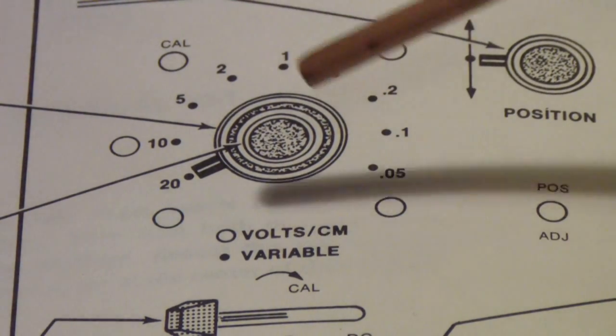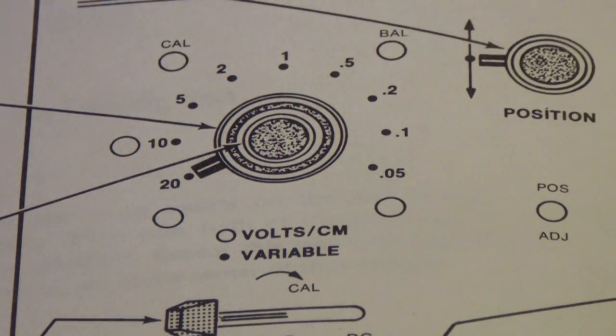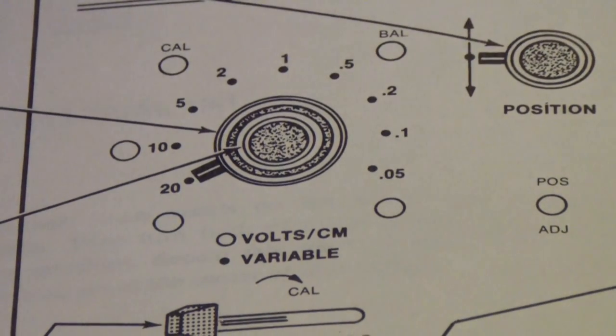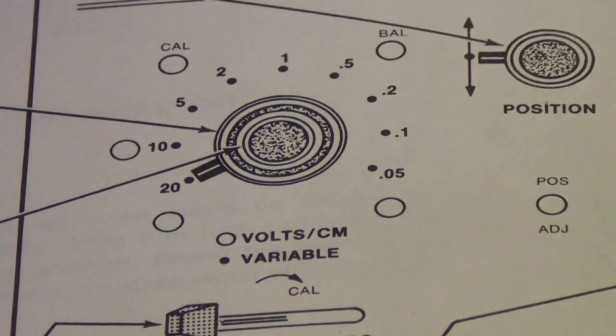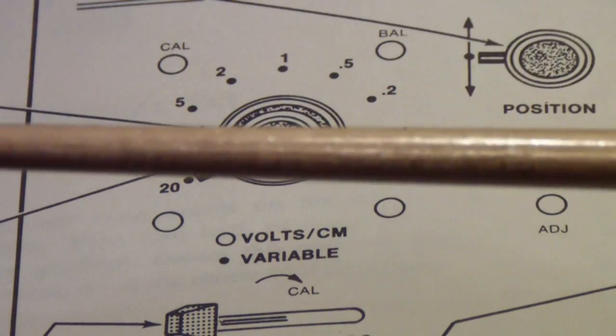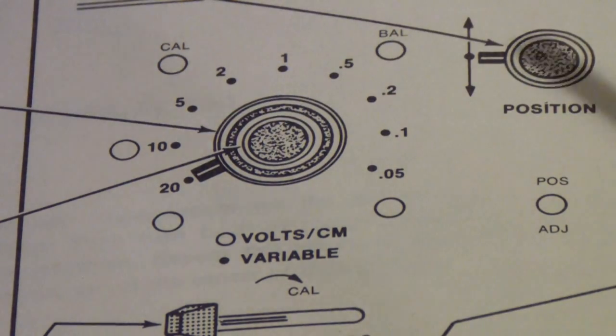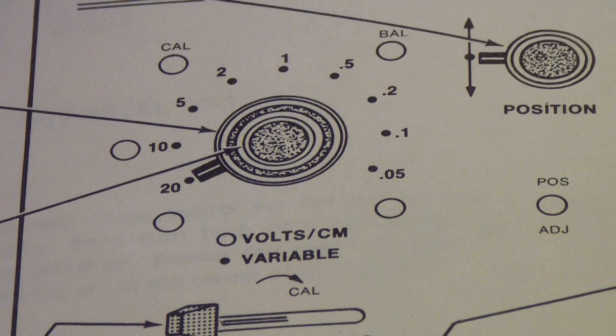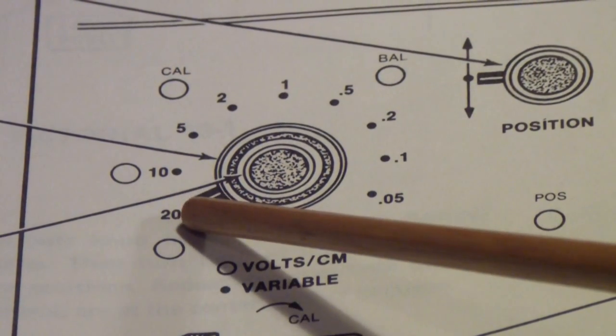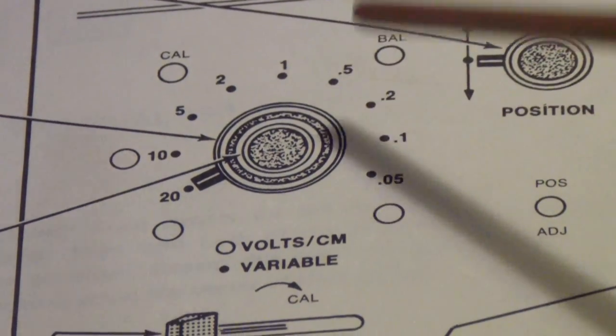But you also would have to calibrate the vertical attenuator. Usually, oscilloscopes like this had a calibration adjustment and a balance adjustment. The balance adjustment, as you would rotate this knob, the trace would move up and down the screen because of offsets in the circuitry. And so the purpose of the balance control was to compensate for those offsets, bring them all back to zero, so that as you went from the highest volts per division to the lowest volts per division, the trace would stay in the center.